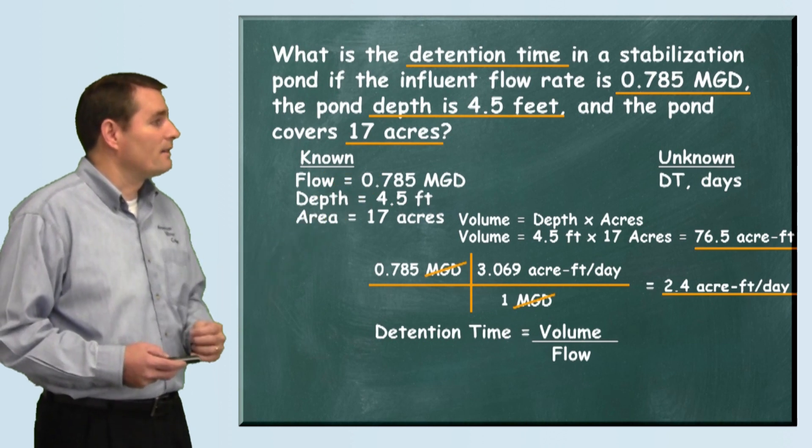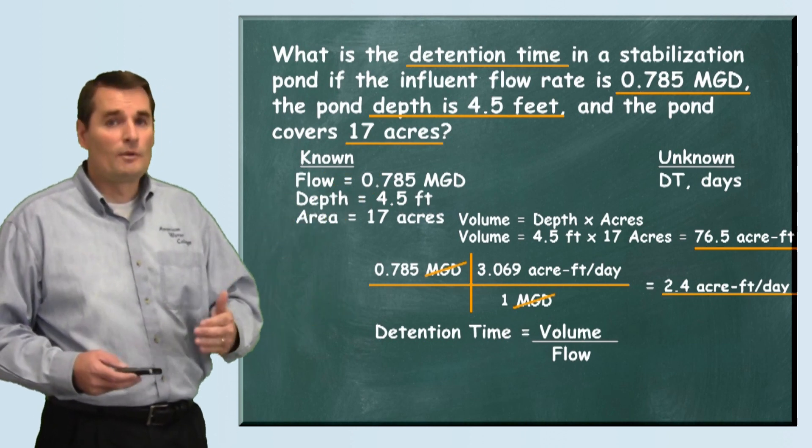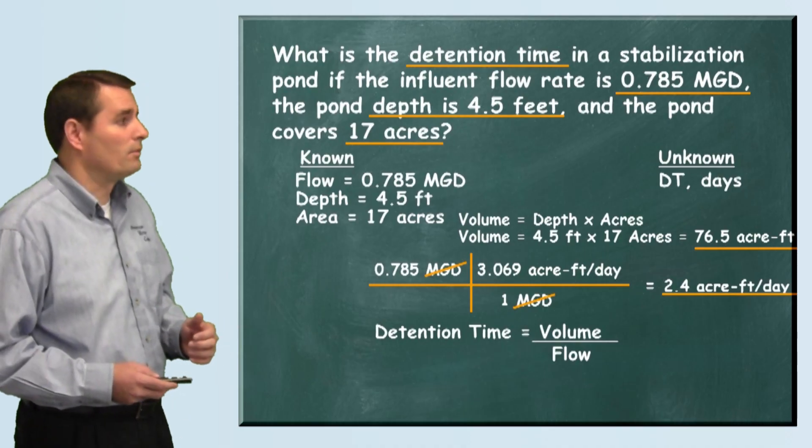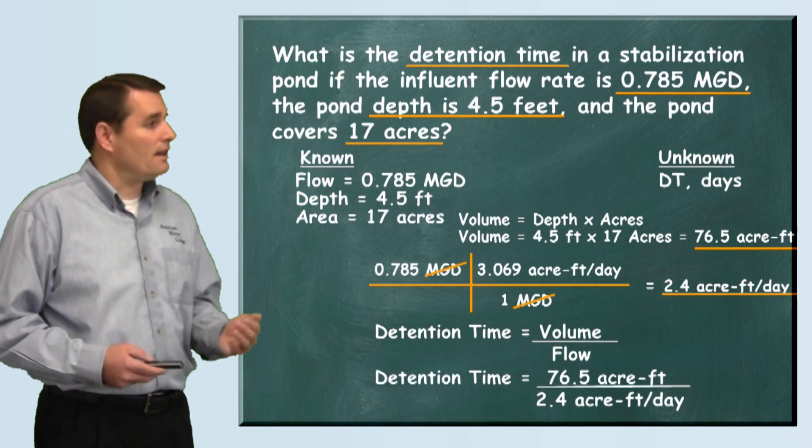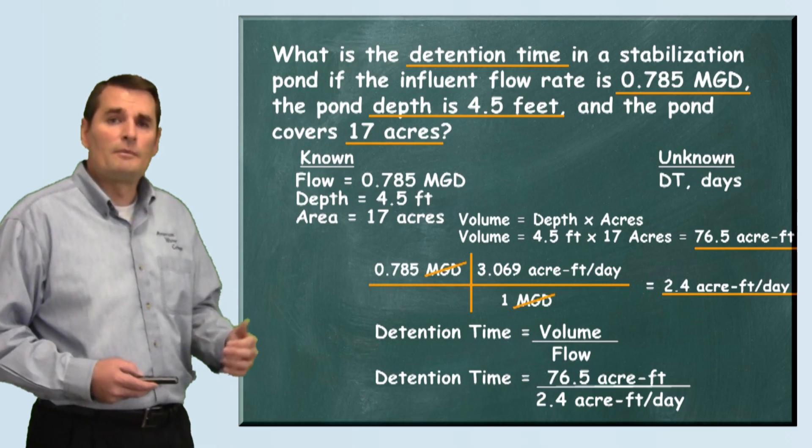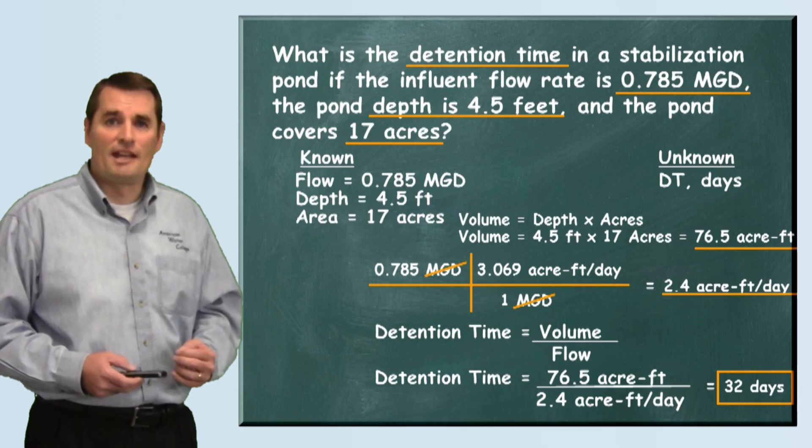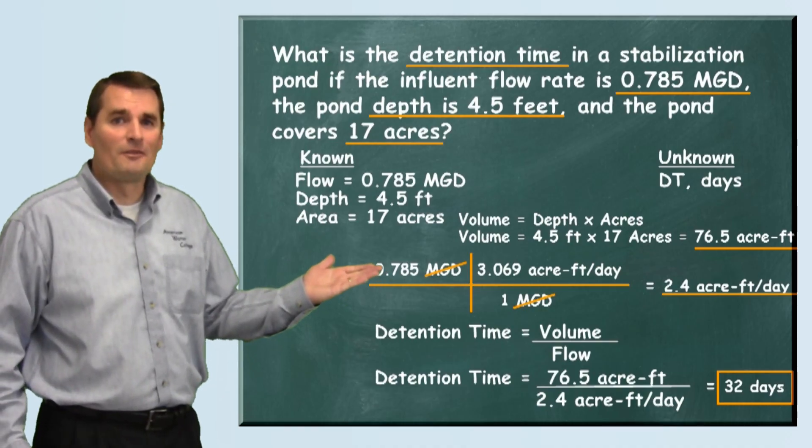Now that we have the volume and the flow going in, we can plug that into our detention time formula to solve this problem. So we put the 76.5 acre-feet on top of the 2.4 acre-feet per day. When we divide this out and do the math we find that the detention time is 32 days. And that my friend is how this problem is solved.